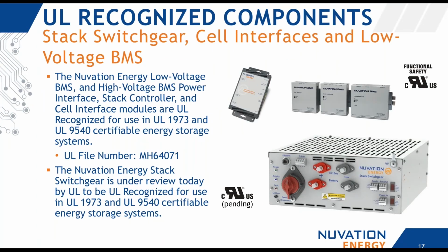And speaking of correct components, our low voltage BMS and high voltage BMSs are recognized. There's a UL file number if you wanted to look it up in the IQ UL database. Our high voltage stack switchgear product is currently under review, so we've got that review ongoing with UL at this moment. Within the stack switchgear, we would find the fuses and contactors, which are part of the list on that previous slide, and in this case, we would be getting them recognized as part of our process. So the stack switchgear can save a lot of that effort on those critical and deeper parts.